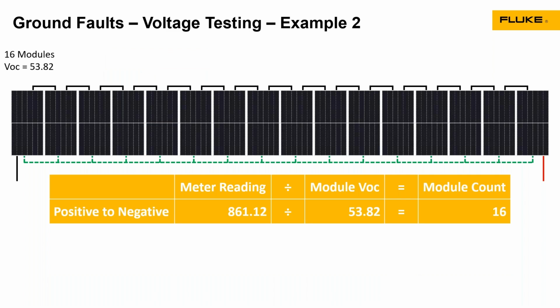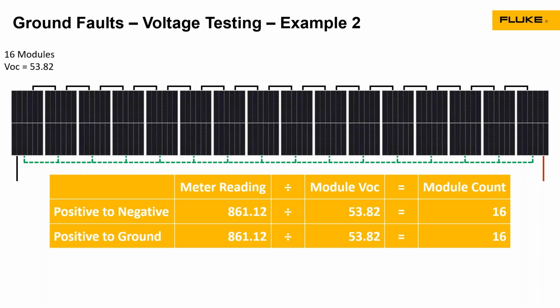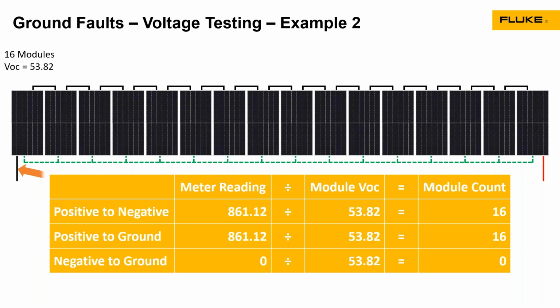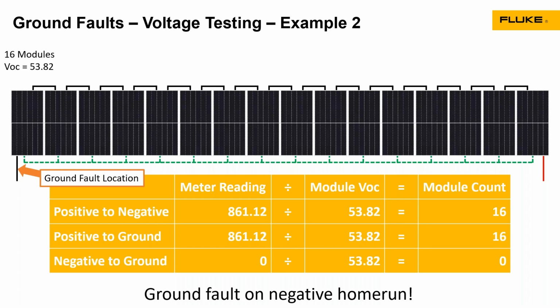Another quick example: positive to negative, same as the last, 16 modules. Positive to ground, I got full string voltage, 861 volts. That's 16 modules' worth of voltage. Negative to ground was 0, which is what I expected. This means that from the positive side, there are 16 modules between the positive side and the ground fault. And on the negative side, there are 0 modules between the negative and the ground fault. This indicates that the ground fault is on the negative home run conductor.